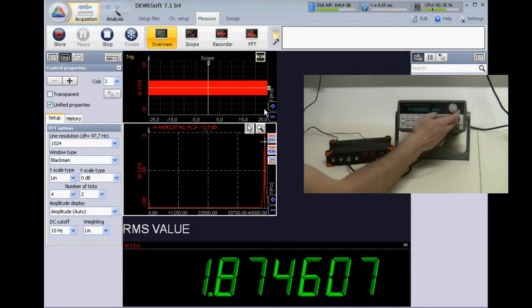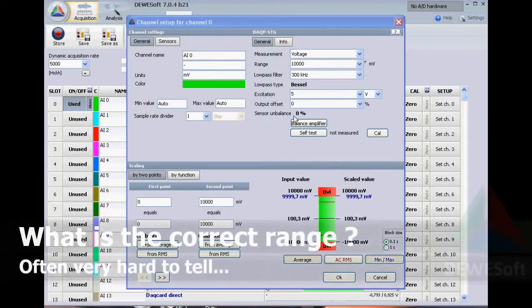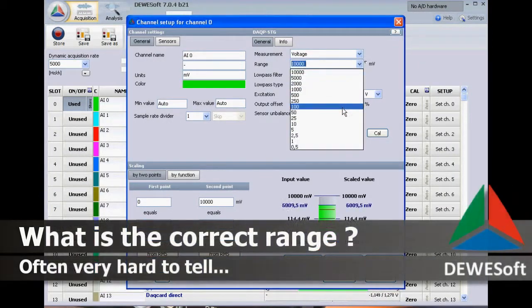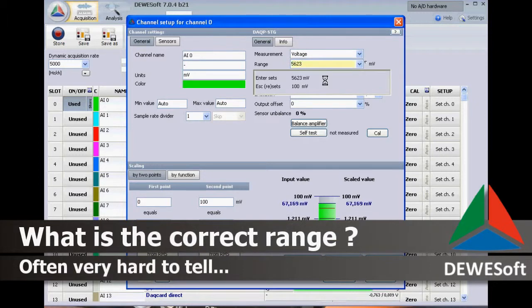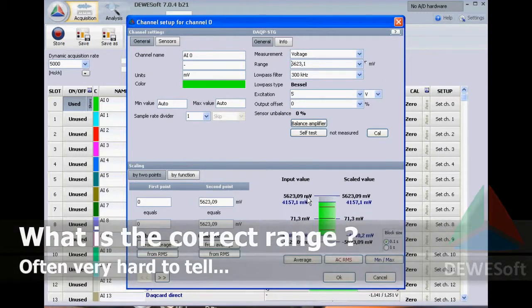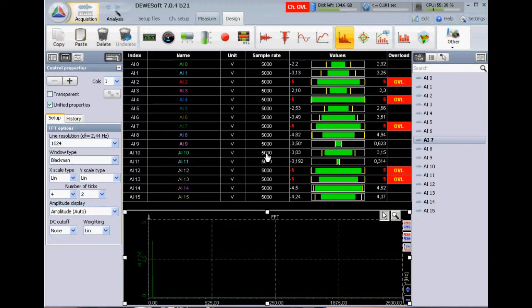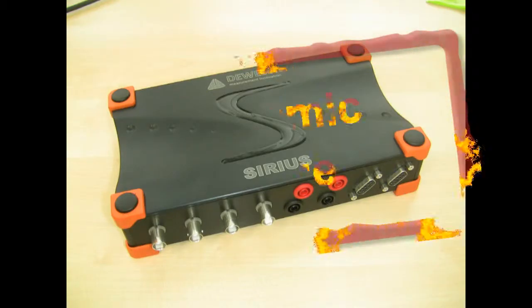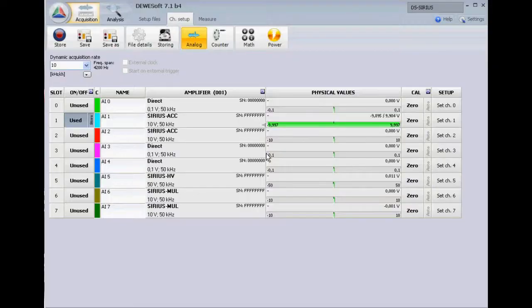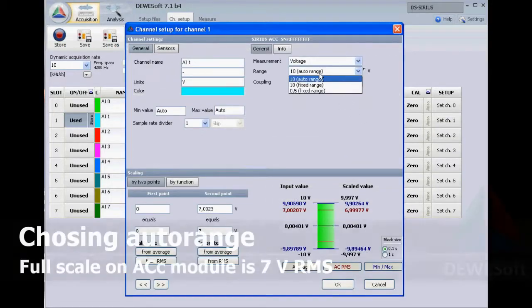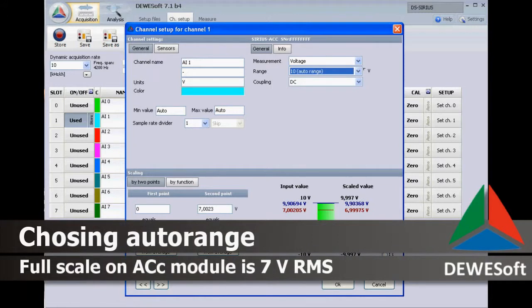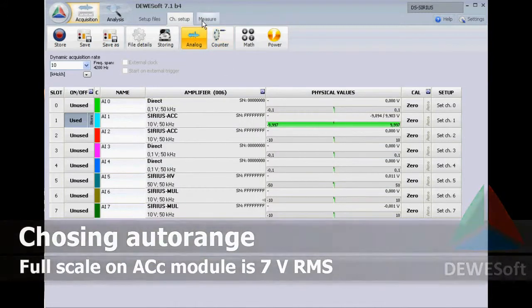What does it mean, dynamic range? It's not uncommon that other amplifiers have 10 or even more measurement ranges. But which one to choose? Often we can't predict what kind of signal levels to expect. In fact, if we had known exactly what to expect, we wouldn't have to measure. Therefore, Sirius has only two ranges, which already have very high precision by themselves, but even those two ranges can be switched automatically during the measurement. So we don't have to worry anymore about overloading the measurement.